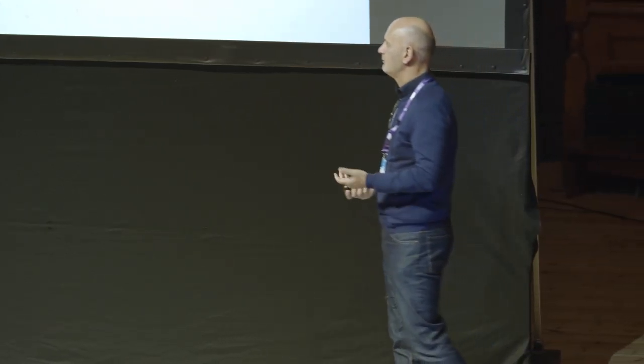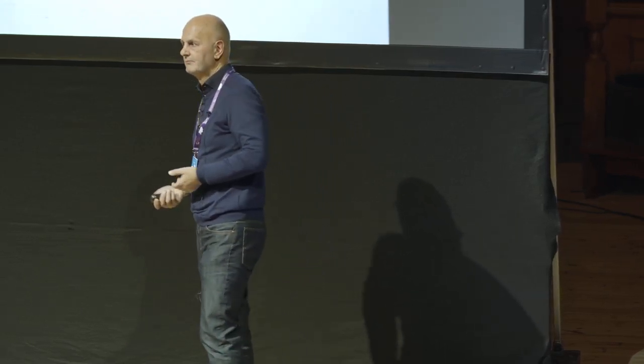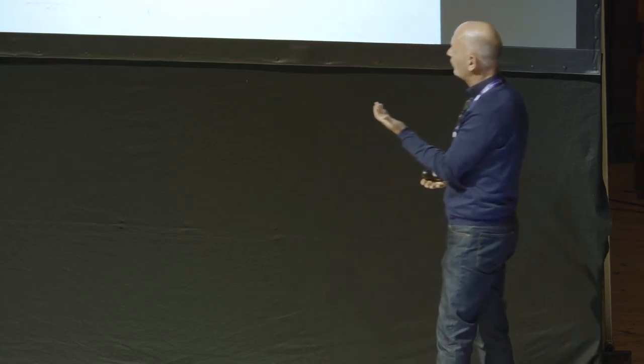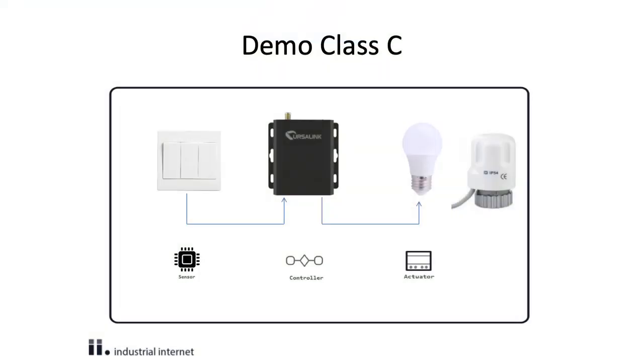This is an interesting device — it's a Class C device made by Ursalink, a Chinese manufacturer. It's both a sensor: it's got digital inputs and analog inputs. It's an actuator, so I can drive a lamp or a valve. It's also a controller — a different breed of device. In it I can react locally to a change of state on the input and drive the output. I can send that information over LoRaWAN, but I don't need to be connected for it to actually operate. It's got a built-in day-of-week scheduler and, being a Class C device, I can drive its outputs as I choose.